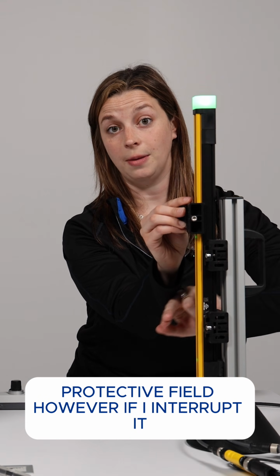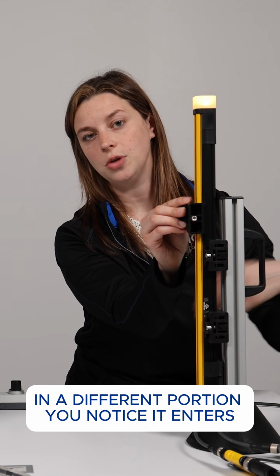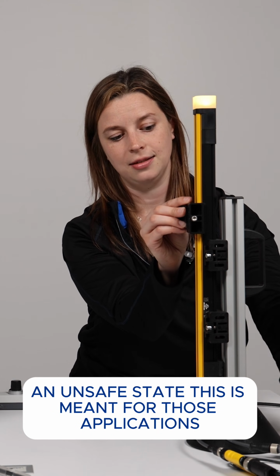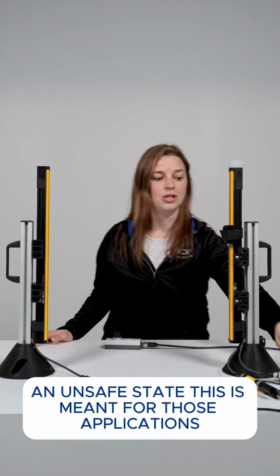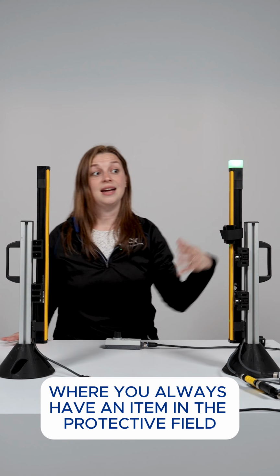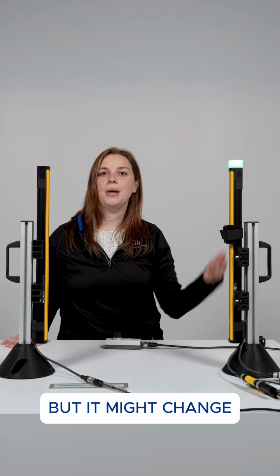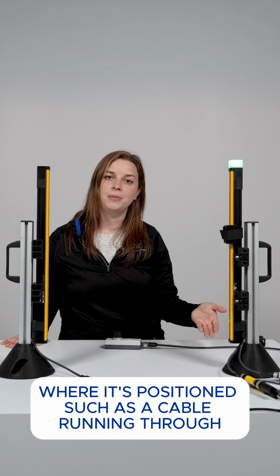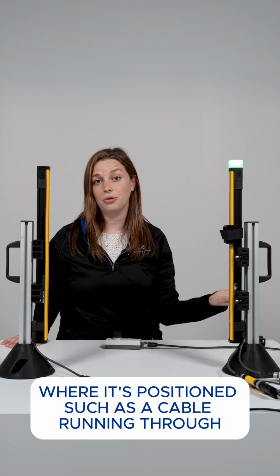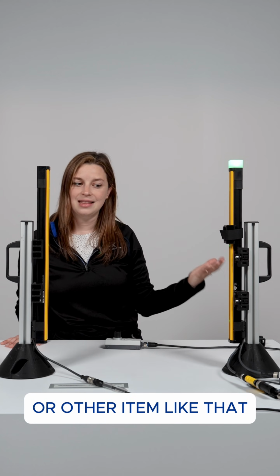What this allows for is the object to shift within the protective field. However, if I interrupt it in a different portion, you notice it enters an unsafe state. This is meant for those applications where you always have an item in the protective field, but it might change where it's positioned, such as a cable running through or other item like that.